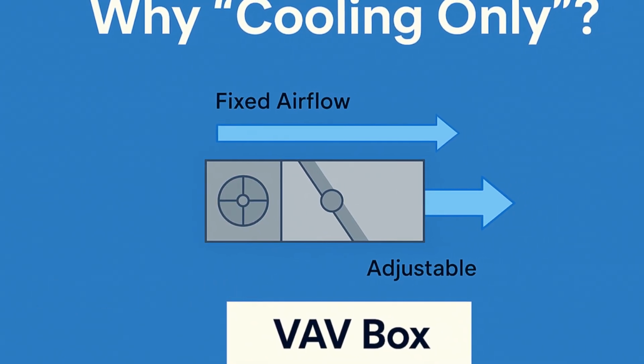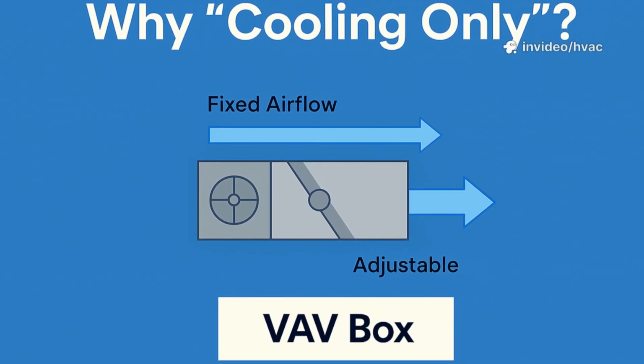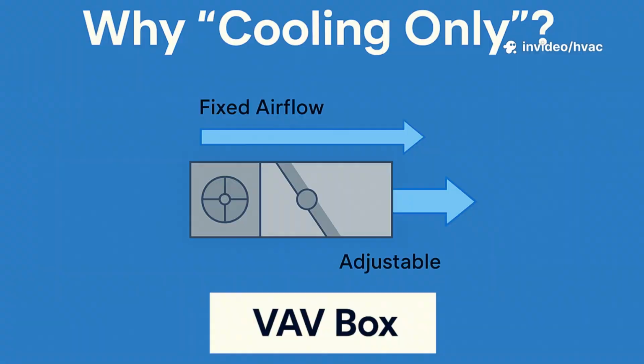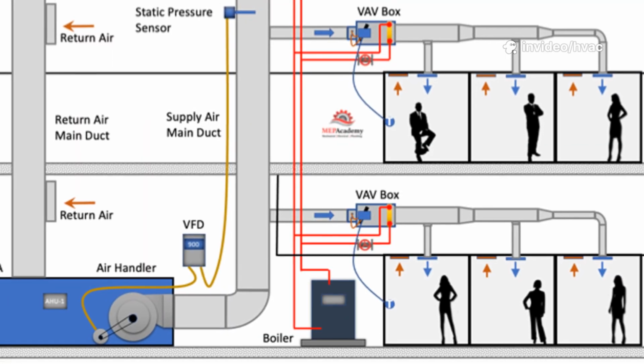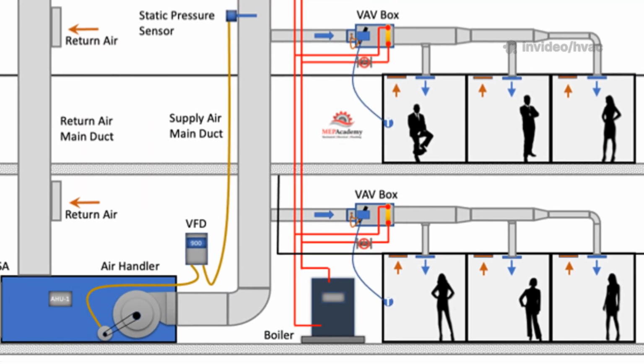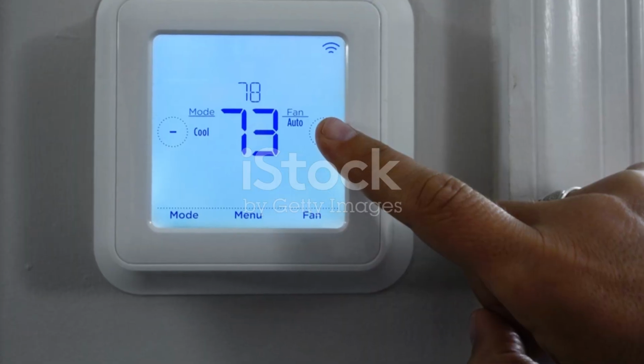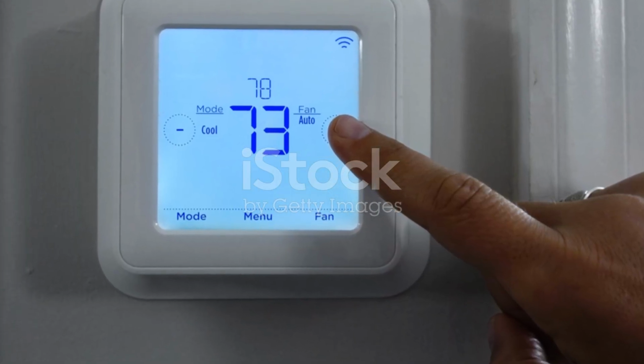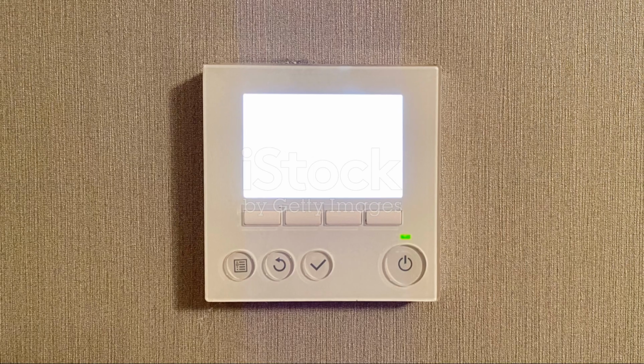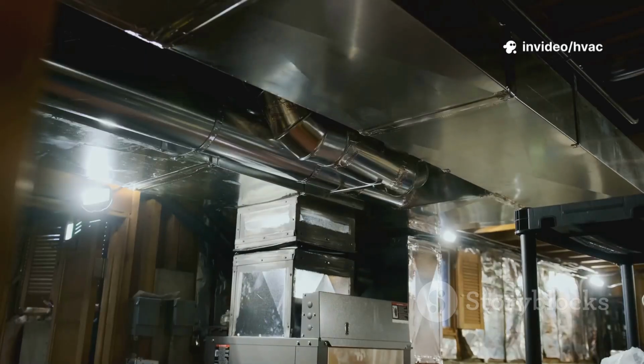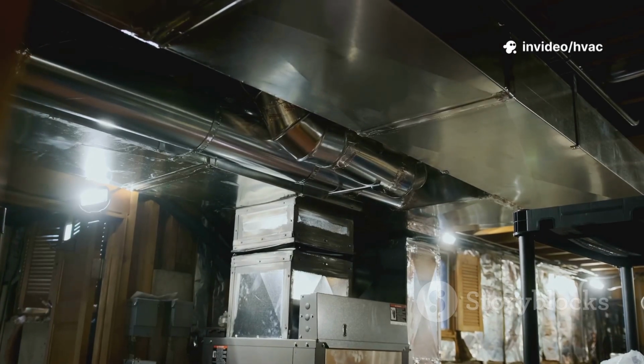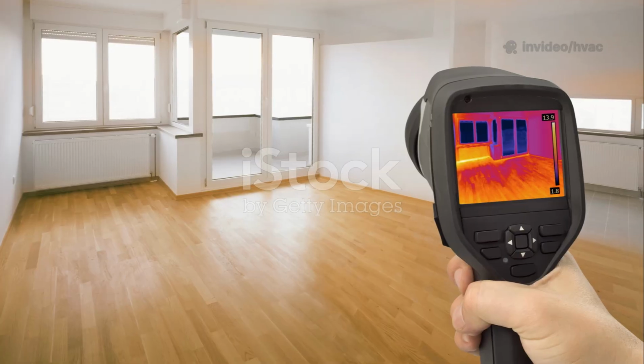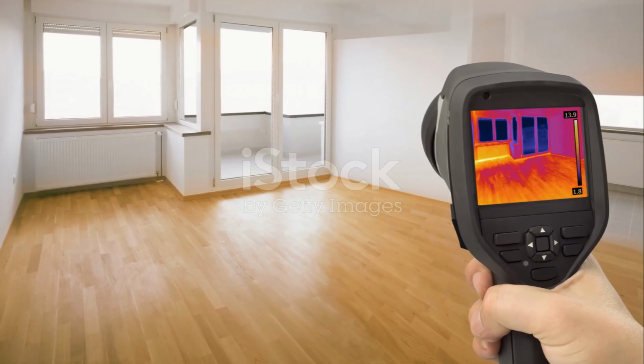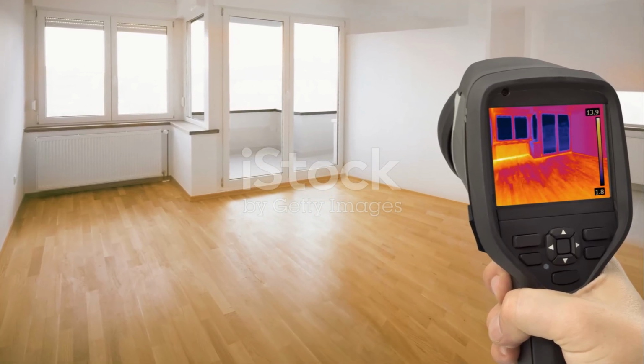To appreciate VAV, let's compare it to its older cousin, constant air volume, or CAV. CAV is like a light switch, always on, blasting the same amount of cold air everywhere all day. If a room gets too cold, it reheats the air, wasting energy by cooling and then heating. VAV is smarter. Think of it as a dimmer switch for your air conditioning. It adjusts the amount of cold air sent to each area based on real-time needs. Hot zones get more air, cool zones get less, no more overcooling or wasteful reheating.